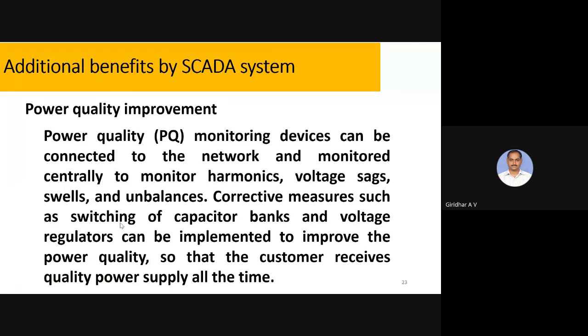We can get power quality improvements. We can monitor harmonics, voltage sags, as well as unbalances, and we can do corrective measures, like switching capacitor banks appropriately. Wherever a sudden voltage dip occurs, you have to switch the capacitor banks. In that way it will be helpful, very fast, appropriate actions can be taken, and the quality of the power supply can be improved at the consumer point.